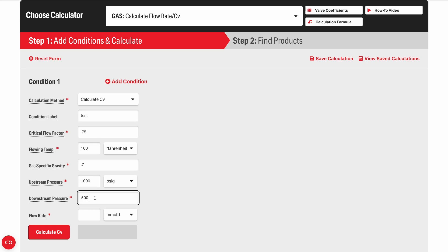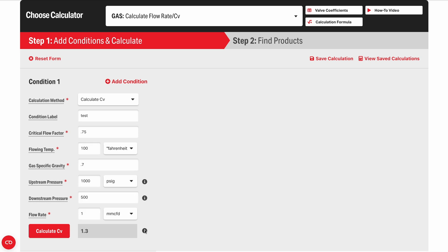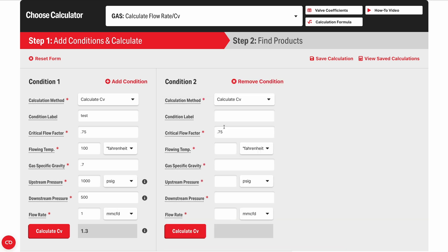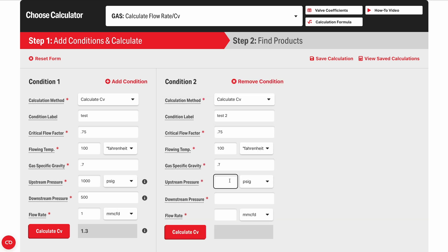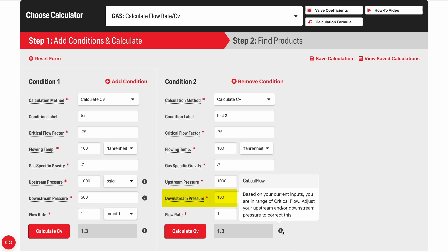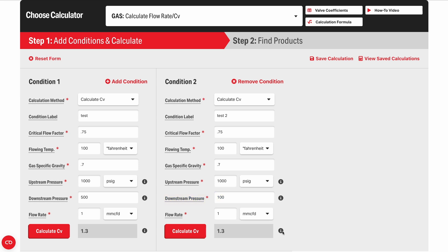Let's look at how this shows up in the Kimray sizing calculator. With certain inputs, you may see a warning for critical flow. This doesn't mean that the valve is sized incorrectly — it's simply a warning that choked flow may occur based on the combination of flow rate, CV, and pressure differential. Decreasing downstream pressure will not increase flow rate once you're at critical flow. Increasing upstream pressure, however, can allow for greater flow rates.